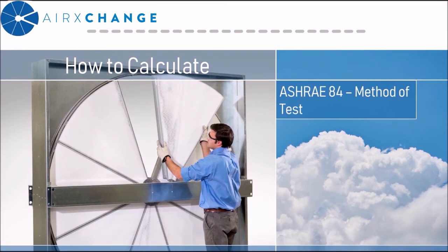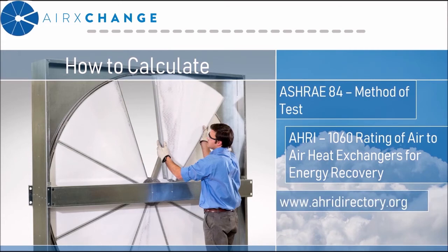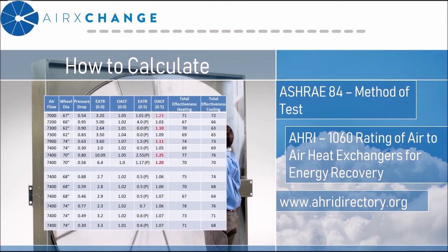ASHRAE Standard 84 provides the method of test, and the rating of energy recovery devices is determined by AHRI Standard 1060. The certified ratings include both EATR and OACF at three different pressure differentials. Anyone who participates in the certification program must rate at a neutral pressure of zero inches, with the other two points chosen by the manufacturer. These values are then published on the AHRI directory for public view. This demonstrates that EATR and OACF are equitable — this chart contains AHRI data from several different manufacturers with different media geometry and desiccants, and these characteristics exist for everyone, not specific to a certain manufacturer.